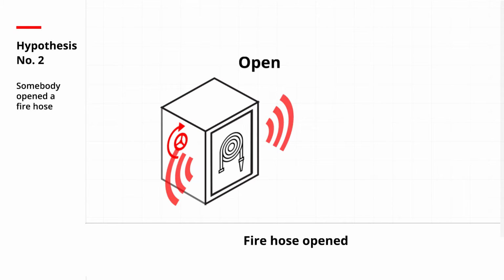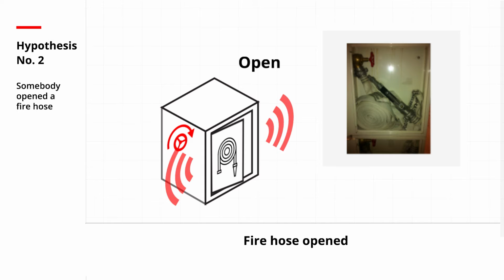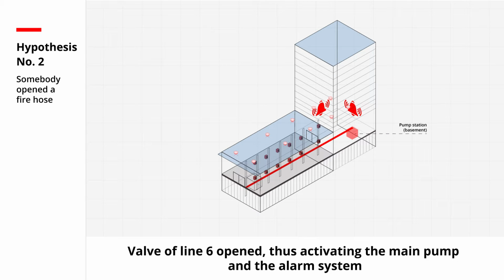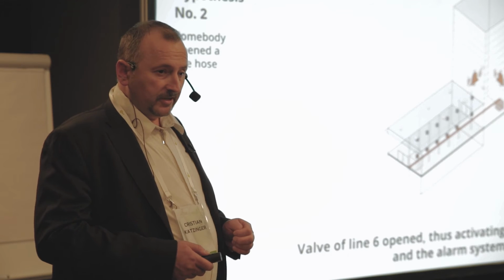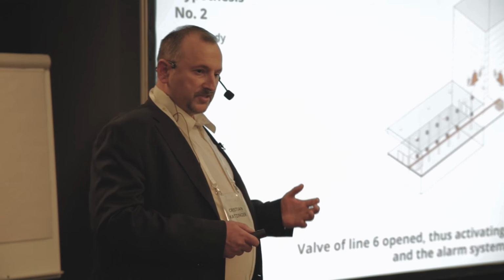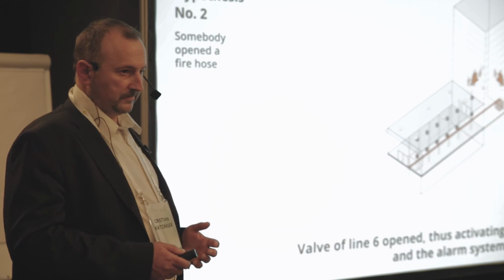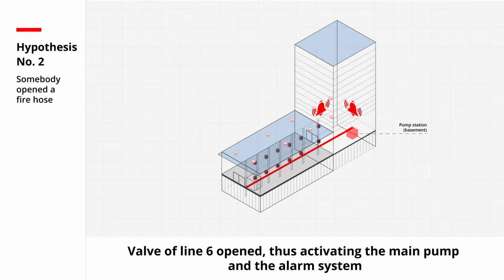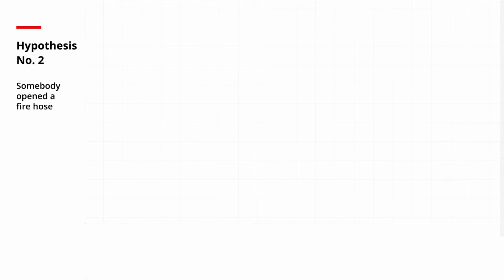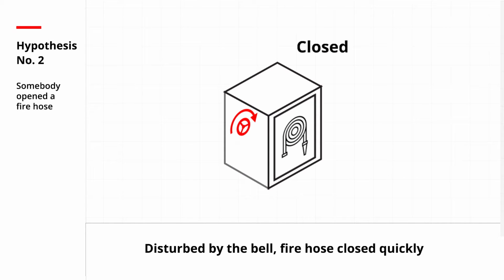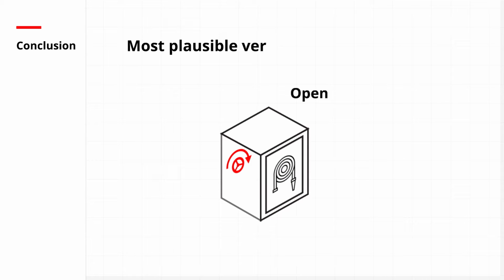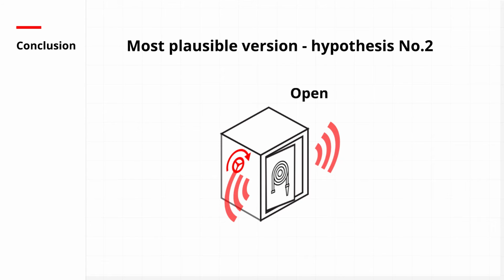Another possibility: we saw that there's an open fire hose cabinet, and we see that there's some disruption here. So there could be the possibility that someone dismounted the hose from the valve and opened the valve, perhaps to get water. That's a speculation, we don't know. The valve was opened, and of course there was a very fast drop of air pressure. And this cabinet is nearer to valve 6 than valve 5. So valve 6 opened and gave the alarm. Disturbed by the bell, the person got frightened and immediately closed the valve. For us, that's the most plausible version and the conclusion for this fire alarm, which wasn't a real one, but a false one.